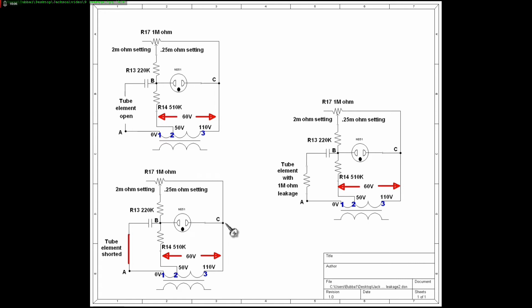Now let's say we had some leakage here. Say we had a tube element and there was 1 megohm leakage through it. A normal tester that didn't have a leakage control wouldn't find that. And it gets interesting here. If R17 is set to the 0.25 megohm setting, a small current flows from transformer point 3 through R17, R13, and R14, which is the voltage divider.